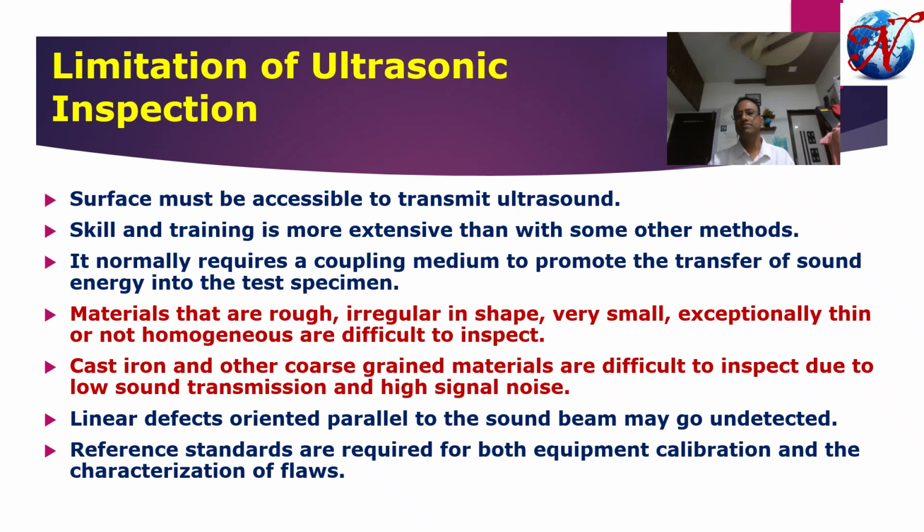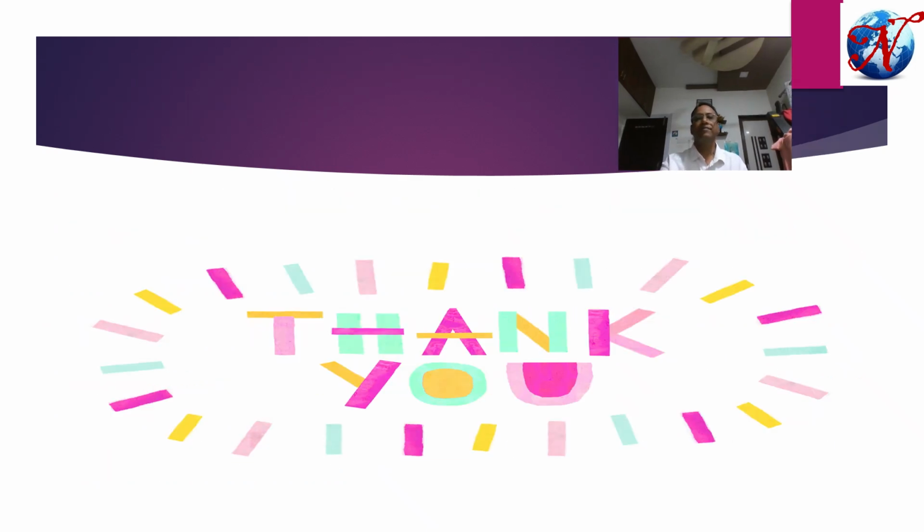So each and every step when we carry out ultrasonic inspection, we need some reference block or reference reflector from where we will take the reference. So that's the basics of ultrasonic inspection. That means the basic principle of ultrasonic inspection is acoustical impedance mismatch. Due to the acoustical impedance variation at the interface of these two materials, some percentage will be reflected back, and that reflected energy will be converted to an electrical signal in the form of echo on the CRT, that means on the ultrasonic machine screen, and we can analyze according to their positions and the nature of the echo.